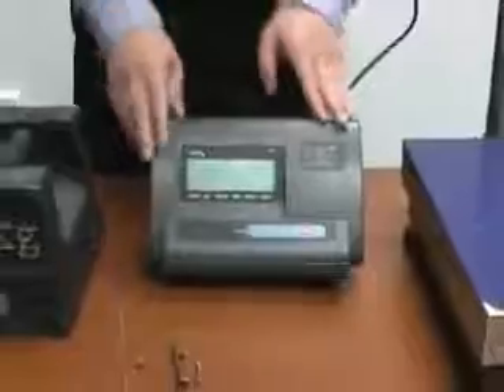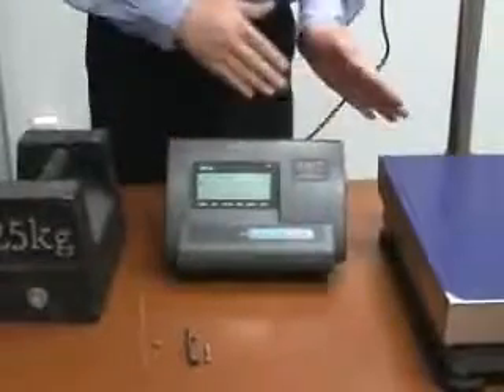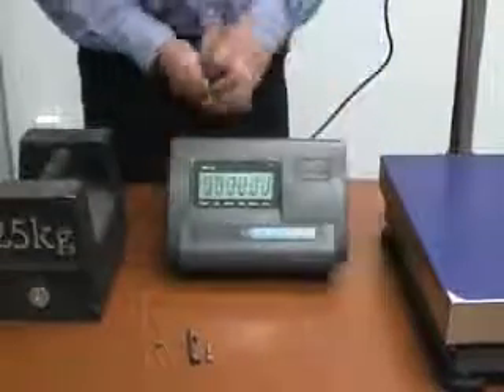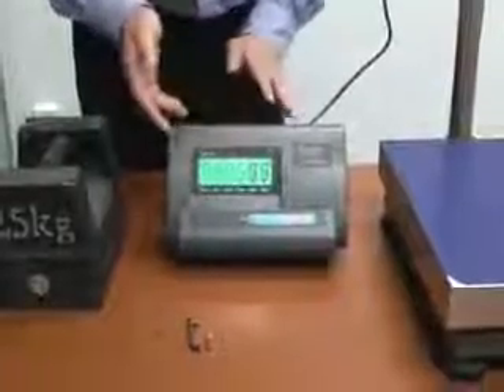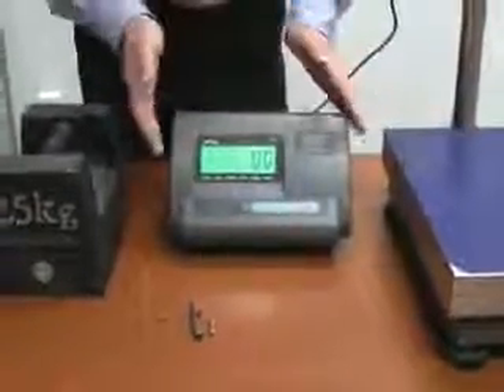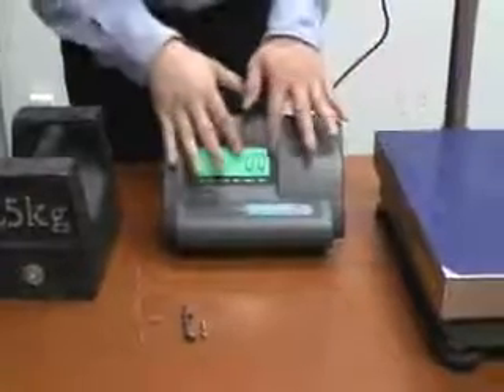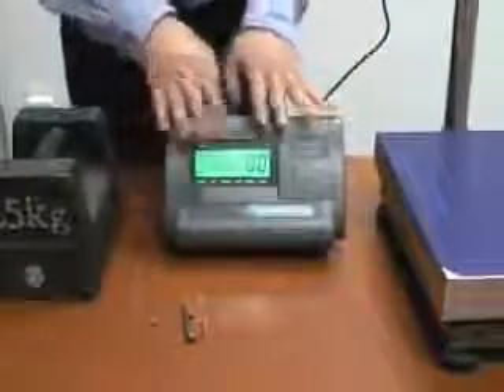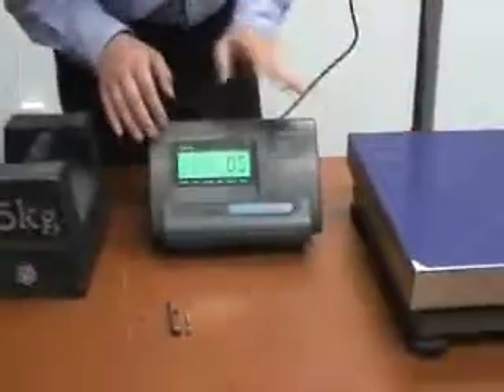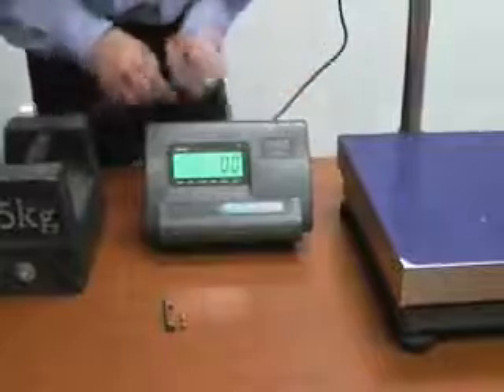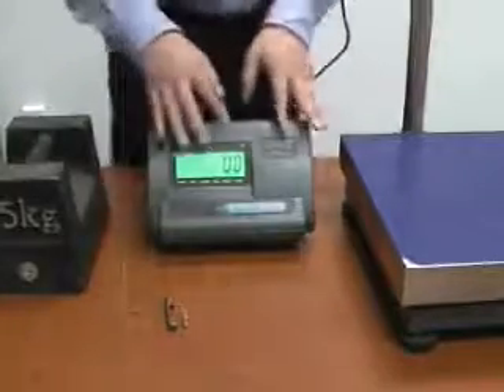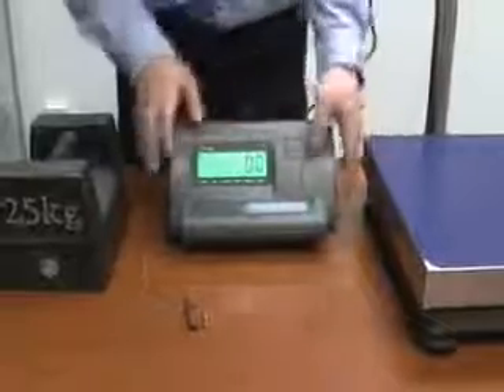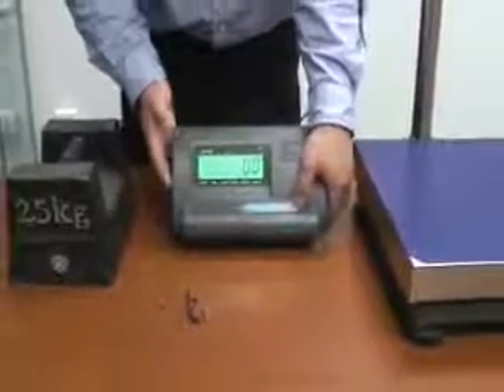Okay. Now to check if the scale is working, you can turn on the scale first, see if it shows 0. It doesn't have to be accurate, but it has to show 0, not an error message. If there is an error message, you cannot solve the problem by calibration. So it has to show 0. And also you can touch the platform, it should give you some reading. Maybe it's not accurate, but after calibration it will be. Okay, now this indicator and the scale base are working. Then we can start the calibration.